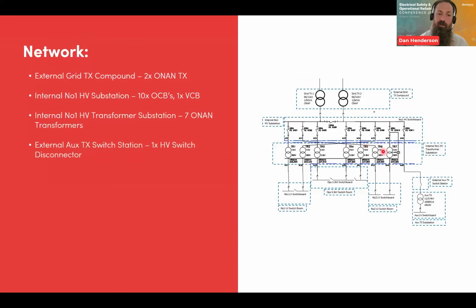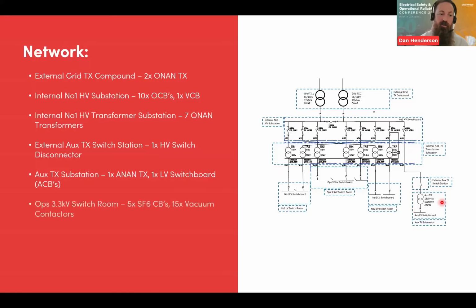We've got an external auxiliary transformer switch station where we've got an external switch disconnector. And then we've got an auxiliary transformer substation where we've got 1 air natural cast resin transformer, an LV switchboard with a 1600 amp ACB. We've got a 3.3 kV ops switch room, which has got 5 SF6 circuit breakers and then 15 vacuum contactors feeding the operational equipment. And then we've got 2 LV switch rooms.